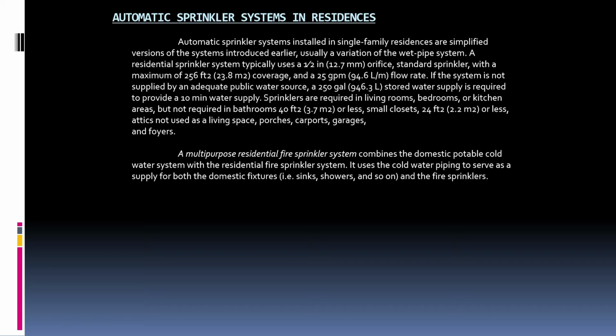A multi-purpose residential fire sprinkler system combines the domestic potable cold water system with the residential fire sprinkler system. It uses the cold water piping to serve as a supply for both the domestic fixtures and the fire sprinklers.